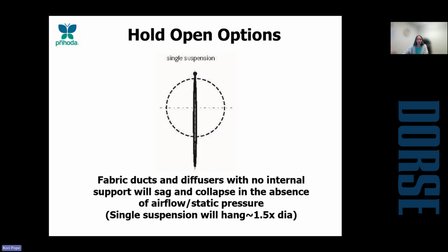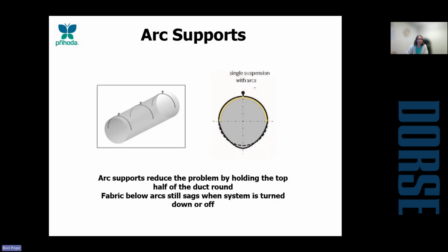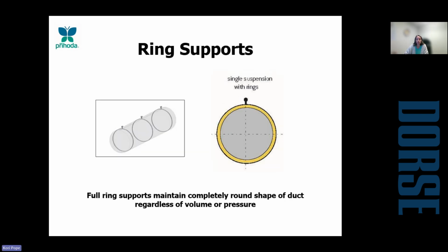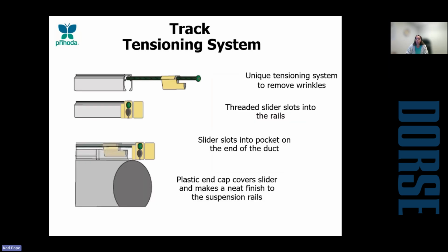So a couple ways that we have to combat the sagging and that inflation pop is with our internal hold open supports. So the first one is our 180-degree internal arcs. So this just is 180 degrees at the top of the duct, and will hold the duct halfway open. However, when that unit turns off, the duct will still sag a little bit and kind of look like an upside down egg. So a better solution, and what we typically recommend, is our full 360-degree internal rings. So these are spaced about every 3 foot. And when paired with our in-track tensioning system, the duct will have about 5% deflation in the system.